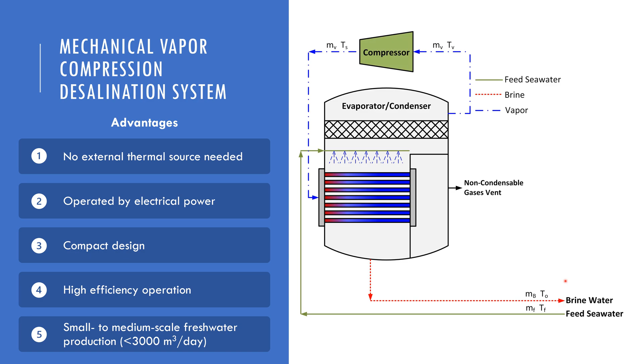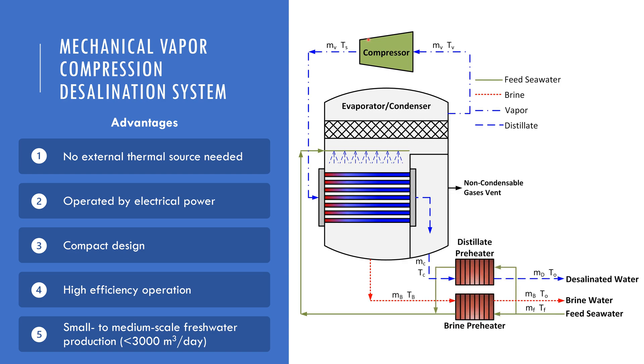Next, the formed vapor enters the compressor to increase its thermal energy by compressing it, and is directed back to the tube side of the evaporator. Due to its higher thermal energy from compression, the compressed vapor releases its heat back to the sprayed water falling outside, vaporizing it and causing the cycle to continue. Consequently, the compressed vapor will condense and is subsequently collected for post-processing and usage. To improve energy recovery, preheaters are installed for the distillate and brine to add thermal energy to the incoming feed streams, thereby improving performance.